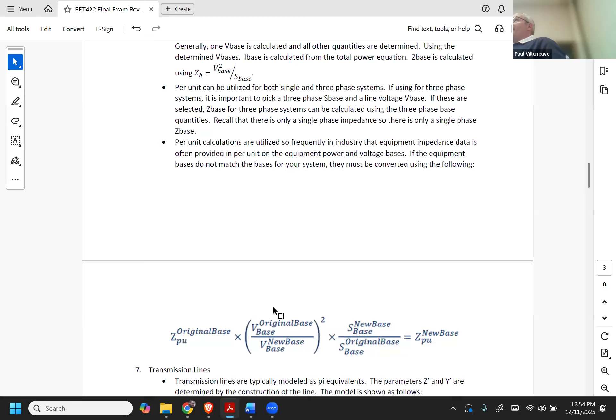So if the equipment isn't on a consistent base—meaning the equipment you purchased has its own original V base and S base, and those don't match the system you're analyzing—you just have to convert it using this equation. It's not complicated: it's basically Z per unit old multiplied by Z base old, divided by Z base new. That's all this equation is doing.